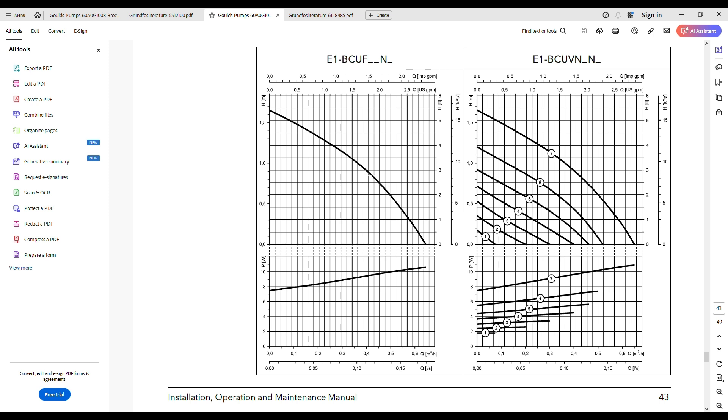Obviously, when you close the valve, you reduce the flow. So what happens is you get the flow at the bottom here on this that begins to reduce, and that takes the pump up this line here, up this curve, all the way up until once the valve is finally closed at zero flow. That's the far end of the curve.